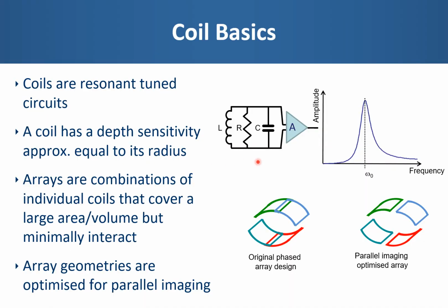The basics of any coil, whether that is for transmit or receive, is that the coils are resonantly tuned circuits. So the coil itself will have inductance and resistance, but then we add additional capacitance to ensure that it has a frequency response near the Larmor frequency. The capacitance also ensures that the transmit coil has a matched 50 ohm impedance to allow proper power transfer from the RF amplifier. Coils will generally have a relatively low Q to ensure that they are still resonant for a range of patient loadings.